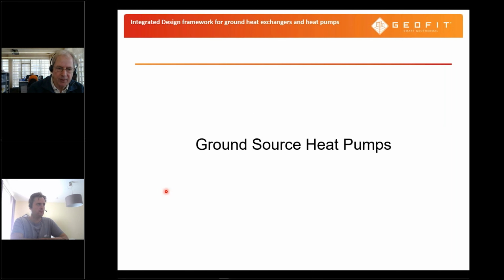So then again, if there are no questions about this part, we go to a part explaining the work that has been done on the actual ground source heat pump, because a ground heat exchanger by itself is usually not sufficient. We need a heat pump to translate the temperature from the source to the temperature in the emission system. And again, I would like to ask Michael to take care of this part, because it is also actually part of another work package 4, that AIT has been working on with the other partners in the project.